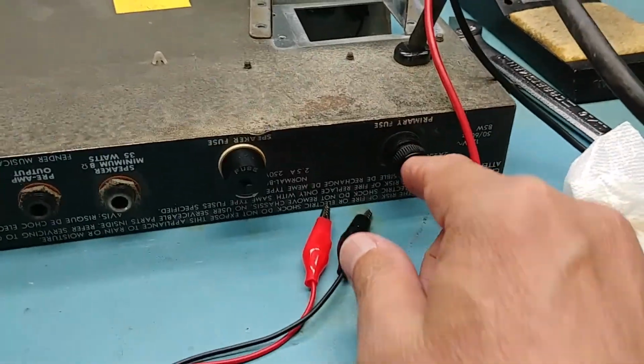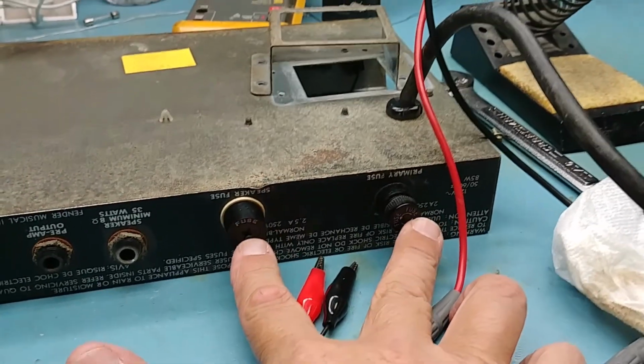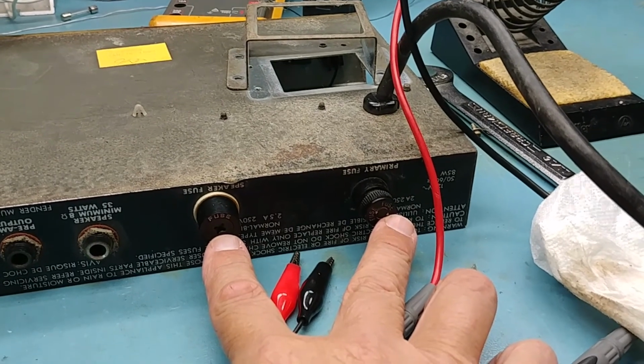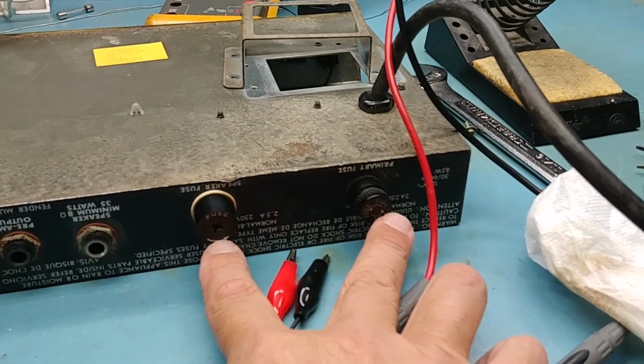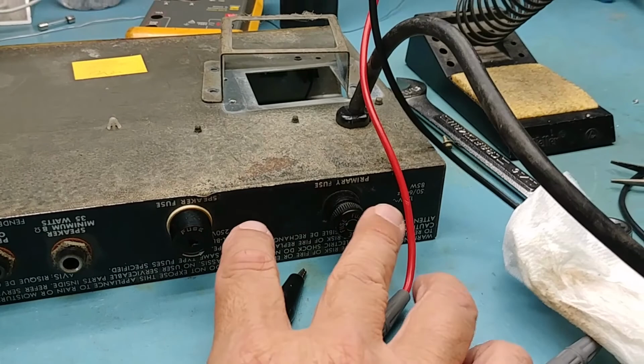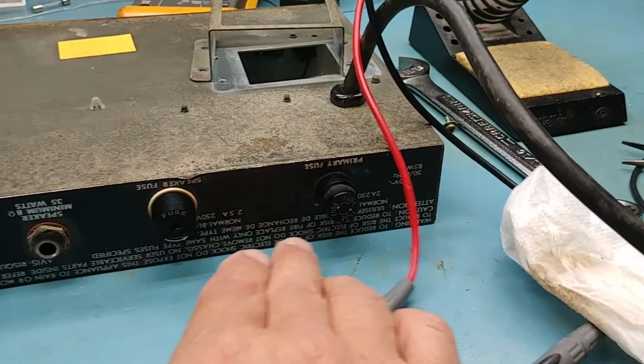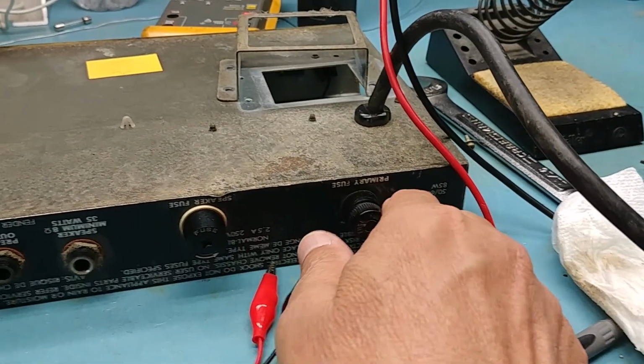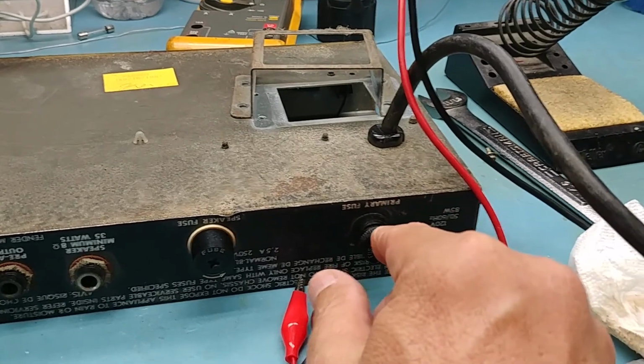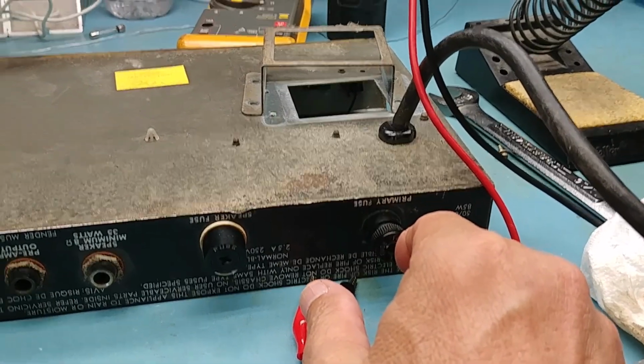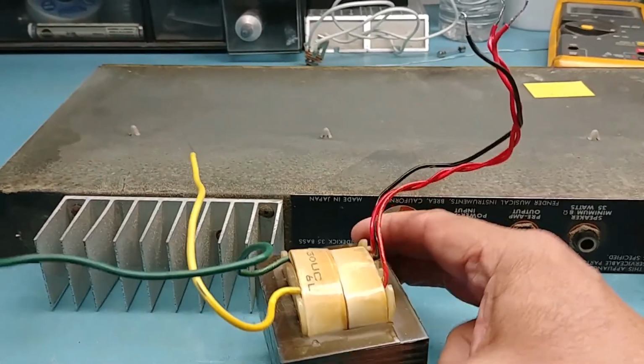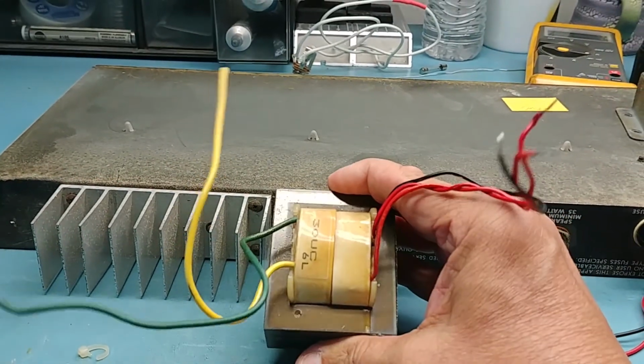And I'm thinking that's a pretty good possibility, because when I got this in, both of these fuses had been changed. One was right, one was wrong. And so I don't know the history of this amp. At some point, somebody could have stuck a 15 amp fuse in here, just not knowing what happened, because the other fuse had burned out, and that could have burned up this transformer. So again, I don't really know, but what I do know is this does need to be replaced.